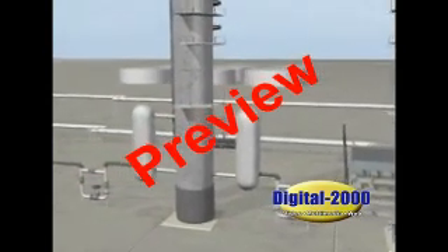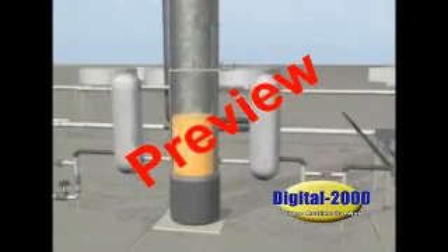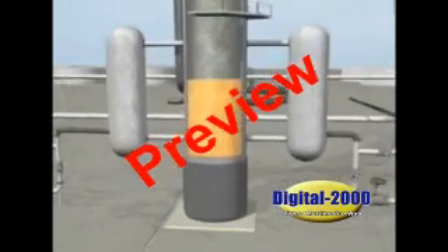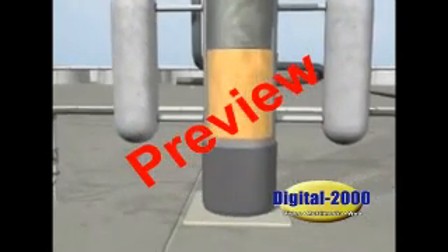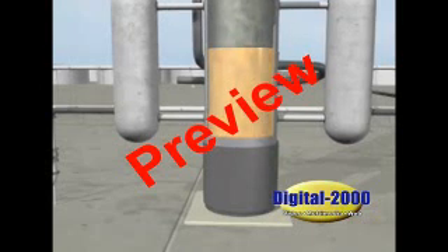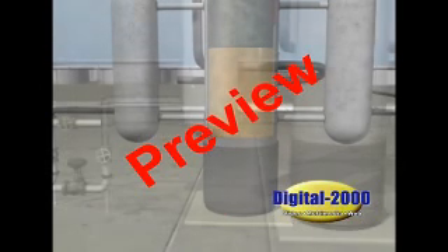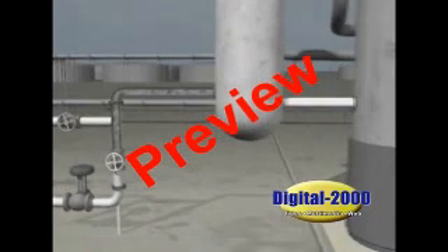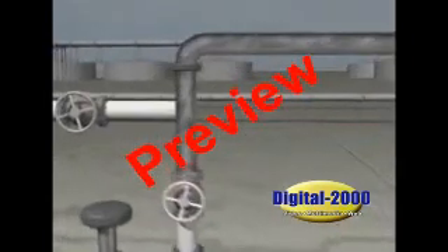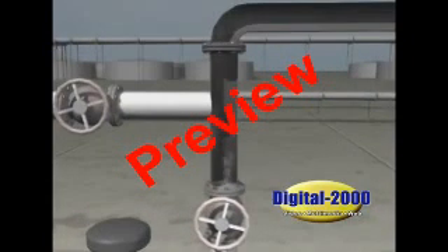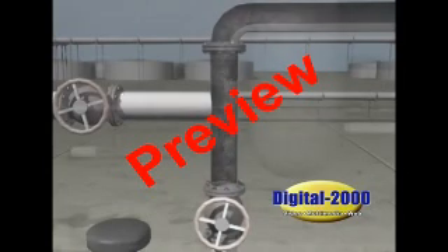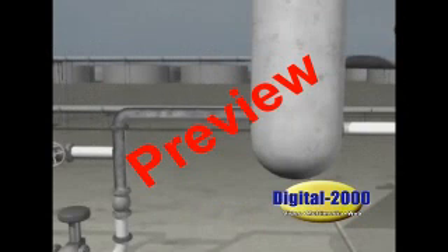Plant operators decided to leave 1,200 gallons of MNT inside one tower during the shutdown. This would be safe at normal temperatures where MNT is stable. The heating was shut down on the 2 reboilers by closing the steam supply valves. But unknown to operators, these valves were corroded and worn. Steam leaked into both reboilers over a number of days, heating up the MNT, causing it to break down and become unstable.